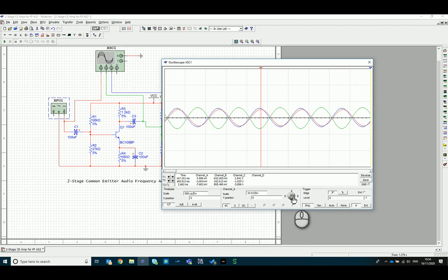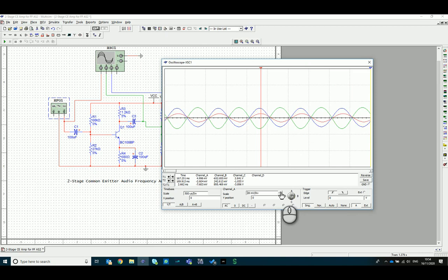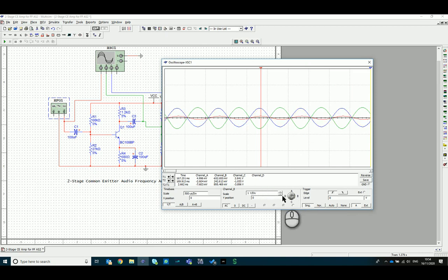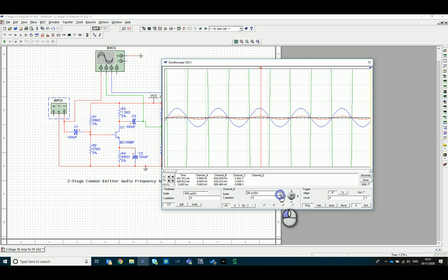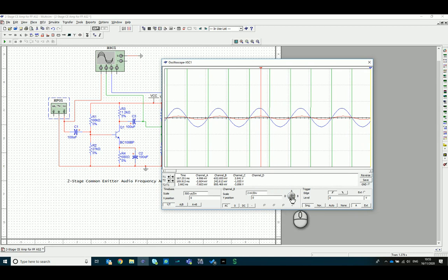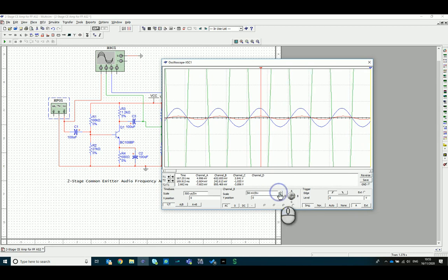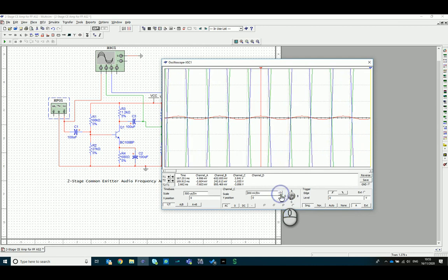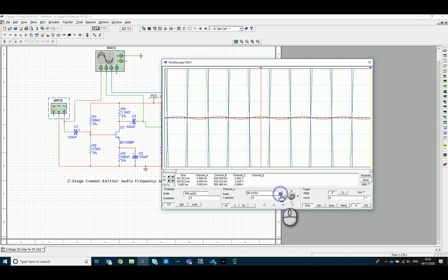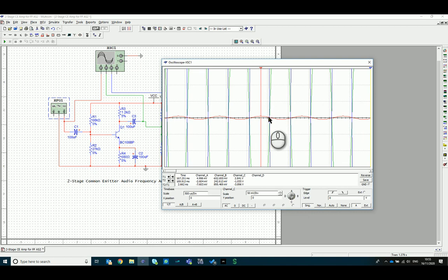Now if I put them all to the same scale, you'll see how comparable they are instantaneously just by the visual standpoint. So if I maybe increase that to say 50 millivolts, I go B and try and put it to the same. Again, you're well off the scale already here, you can't really read anything. And this one, for channel C, if I go down to 50 millivolts, you see that the red and the, or sorry, the blue and the green one, they're just not even readable anymore. That's why we have to be able to change the scales for each of the channels.